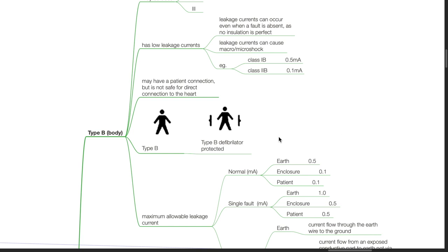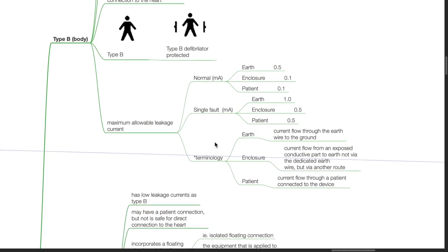Type B equipment may have a patient connection but is not safe for direct connection to the heart. These are the symbols for type B and type B defibrillator-protected equipment. Maximum allowable leakage current terminology: Earth refers to current flow through the earth wire to ground. Enclosure refers to current flow from an exposed conductive part to earth, not via the dedicated earth wire. Patient refers to current flow through a patient connected to the device. At normal conditions: Earth 0.5, enclosure 0.1, patient 0.1 milliamps. During a single fault: Earth 1.0, enclosure 0.5, patient 0.5 milliamps.